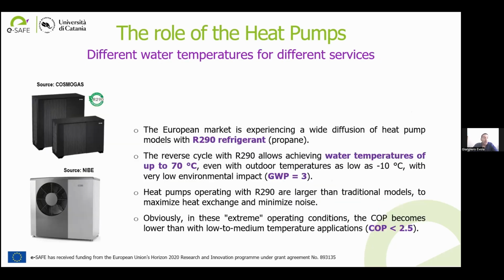One other thing I can mention is that the European market of heat pumps is experiencing a wide diffusion of heat pumps with environmentally friendly refrigerants, with very low global warming potential. One of these refrigerants is propane, R290. Propane is actually a fuel, so it is flammable, but it is also a very good refrigerant fluid. It can be used with the due security devices, let's say, even in heat pumps as a refrigerant.